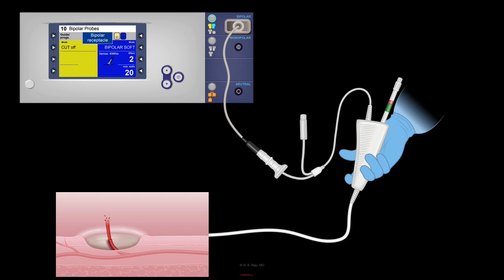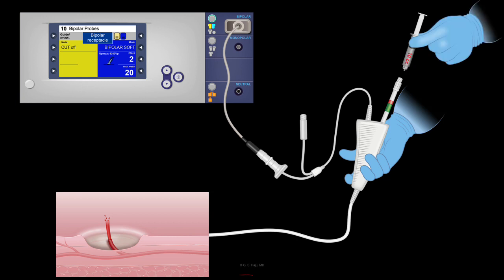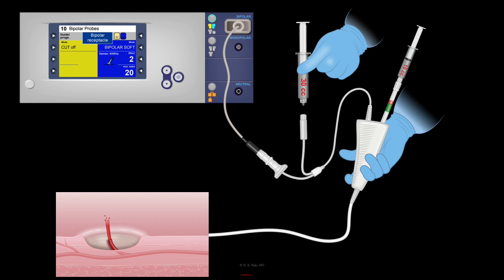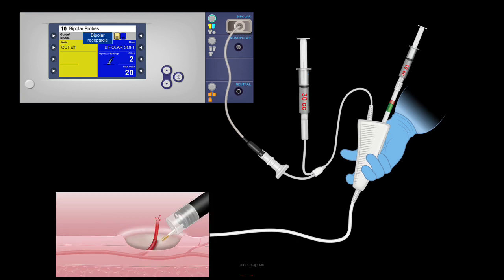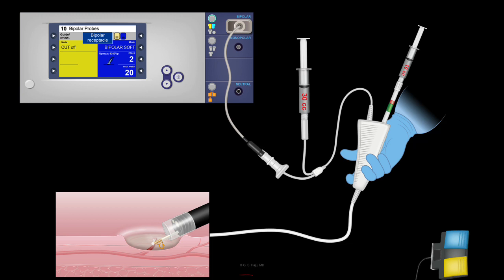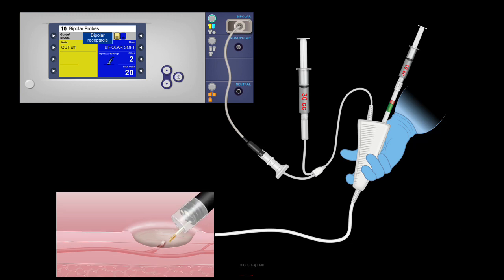And this device has a couple more functions not related to the electrosurgery. One is you could inject epinephrine, or you could flush and clear the blood with another syringe, right? Those are the other outlets. And when you're ready, you activate the bipolar probe by pressing on the blue pedal, that is for coagulation. Press on the blue pedal and apply the probe to the vessel firmly to create what is called coaptive coagulation. That means you apply the pressure so that the vessel walls kiss each other, so that when you apply current, you basically obliterate the vessel.